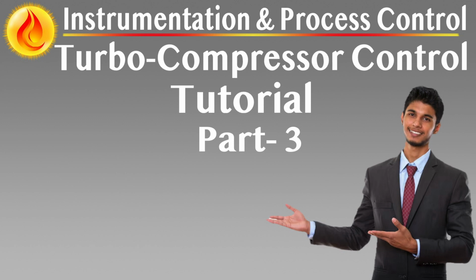This function is embedded within the unit control panels, UCPs, and coordinated centrally through the Common Control Panel, CCP, for multi-train systems. Key elements of anti-surge control. Stage-wise control logic. Each compressor stage is equipped with its own anti-surge controller that continuously monitors suction pressure, discharge pressure, flow rate, and gas properties, e.g. molecular weight, compressibility.